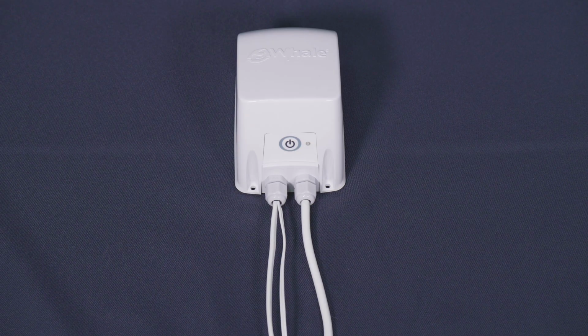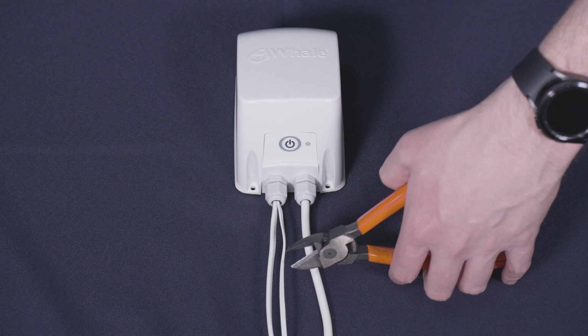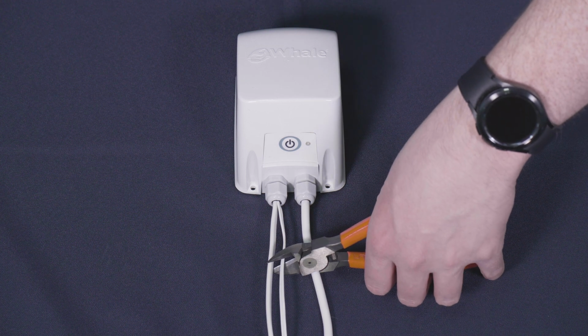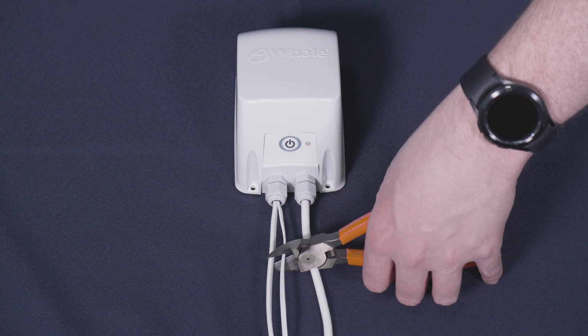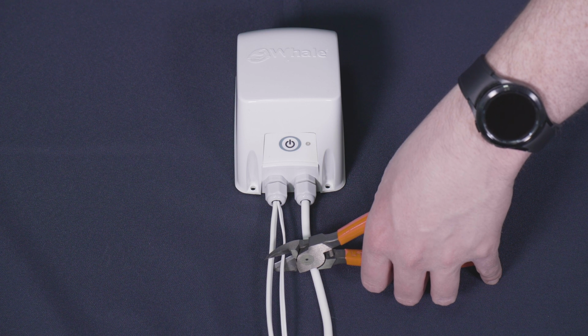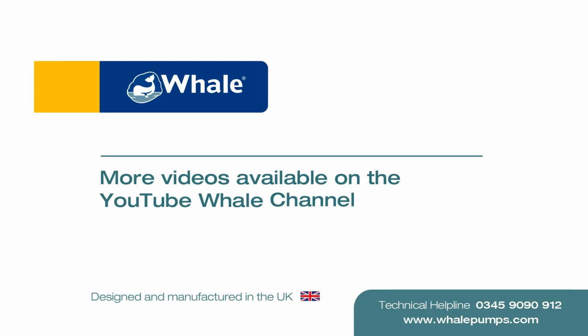Before replacing the transformer, please cut the bell wire about 2 inches from the transformer to ensure the cable has not been damaged behind the wall. If the transformer continues to run, you have confirmed the transformer is at fault and will need to be replaced. That concludes the guide for fault diagnosis of the Whale Switch Connect transformer and flow switch.